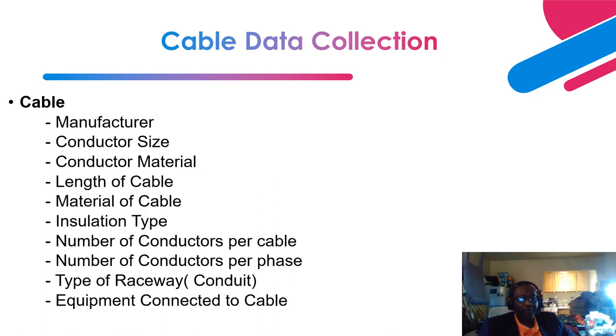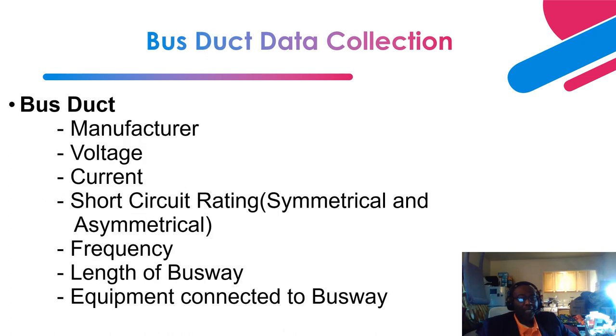Now let's talk about cable data. What you need to collect for cables includes: manufacturer, conductor size, conductor material, cable length, cable material, insulation type, number of conductors per phase, number of conductors per cable, type of raceway (bus, cable, or conduit), and the equipment connected to the cable. For bus duct data collection, you need the manufacturer, voltage, current, short circuit rating (symmetrical and asymmetrical), frequency, length of the busway, and equipment connected to the busway. Bus duct impedance is very low — close to zero — so impedance data is generally not needed.